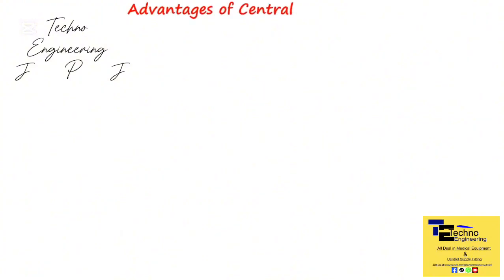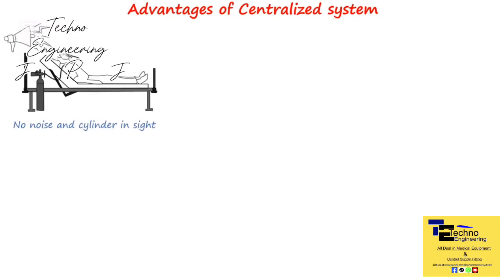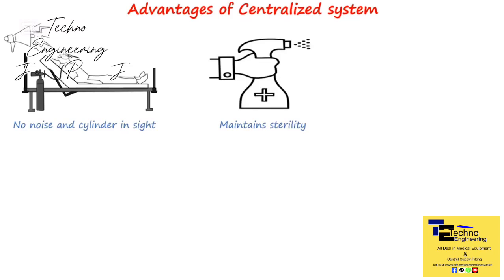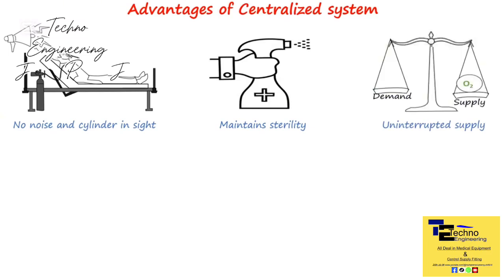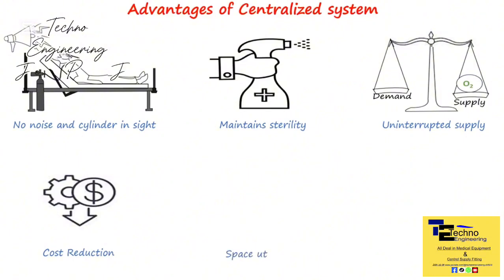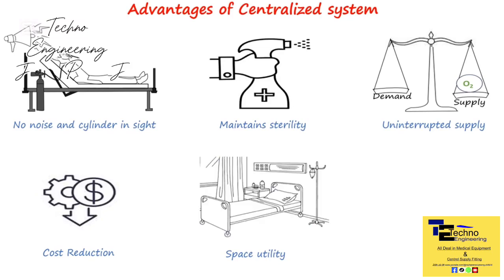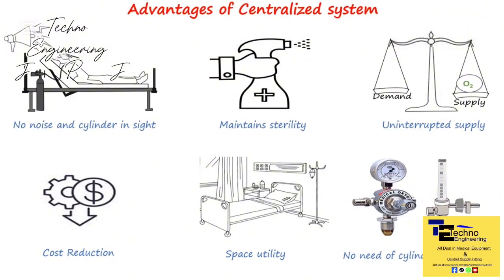The centralized supply system offers several advantages over cylinders. Firstly, it eliminates both visual disturbances and the noise associated with unsightly cylinders at the bedside. Sterile areas are protected from potential contamination caused by the movement of cylinders. The system's main advantage over cylinders is the uninterrupted supply of gases, while also reducing transportation costs and the labor efforts required for transportation. Space utilization is optimized, reducing facility overcrowding. Furthermore, the system centralizes gas distribution, eliminating the need for individual pressure regulators and avoiding the wastage of residual gas in the cylinder.